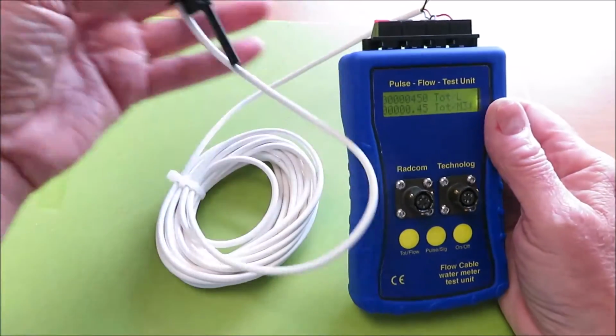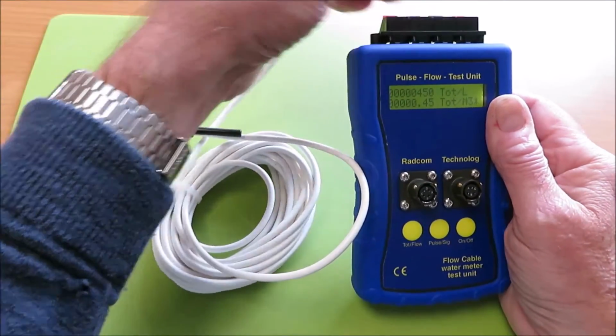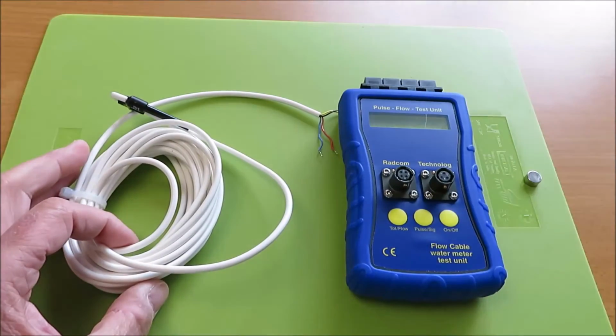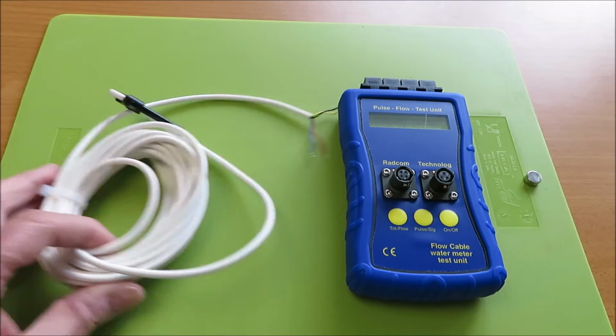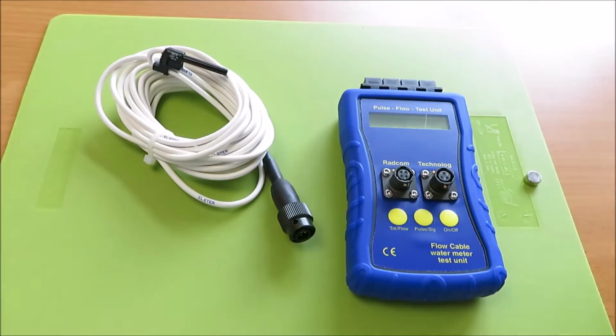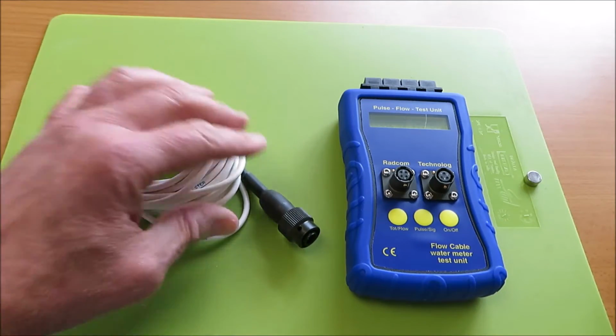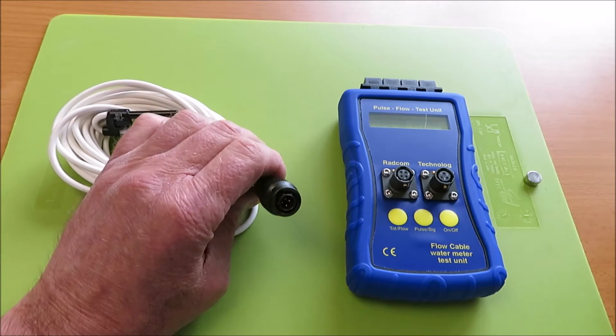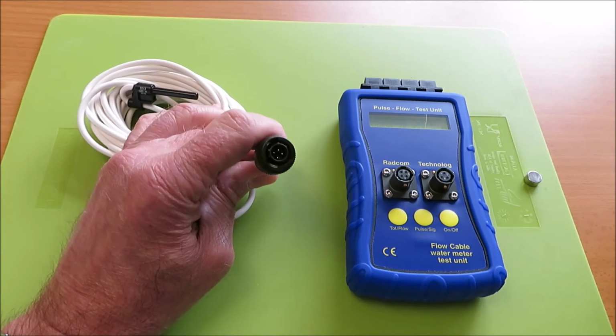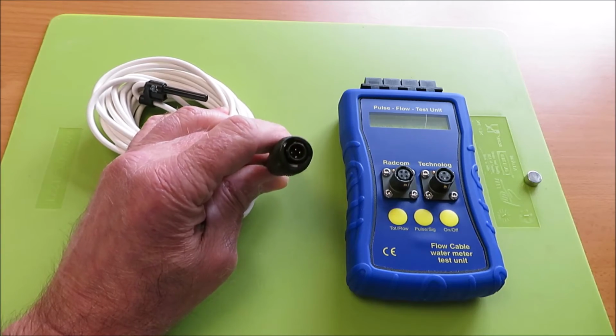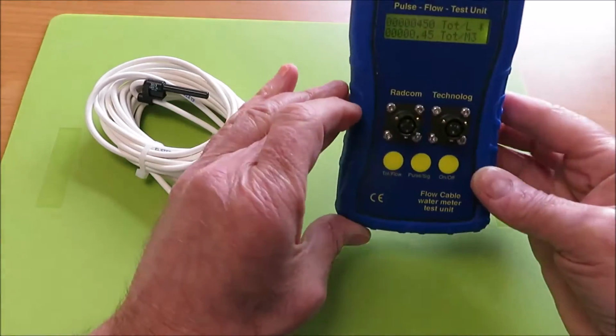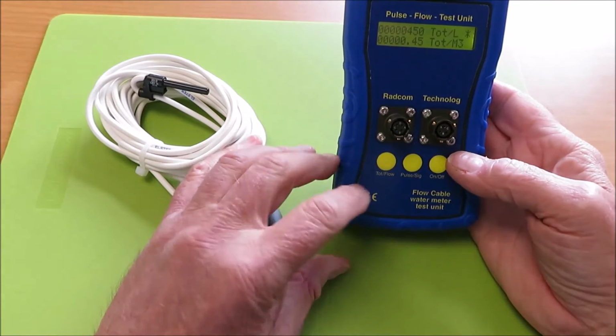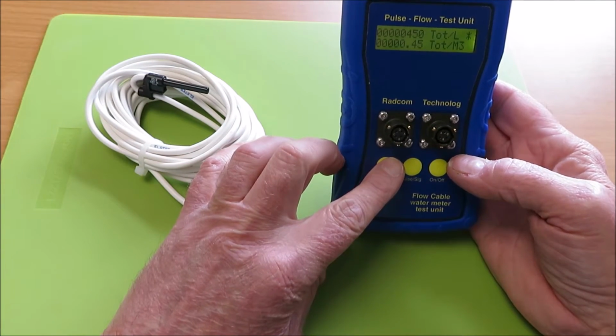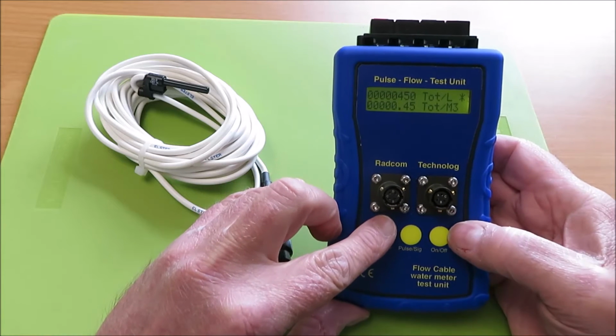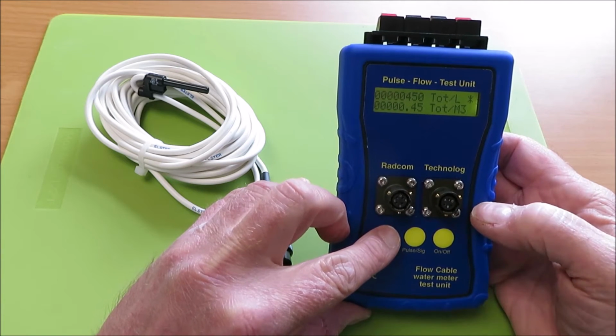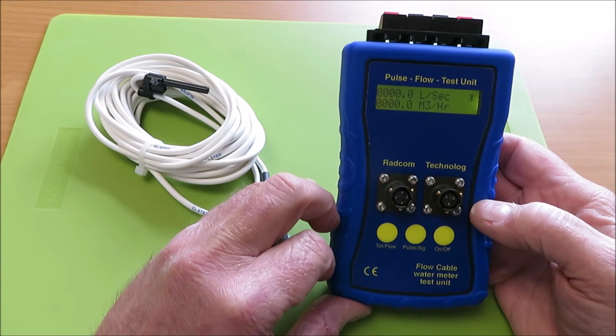Now equally, what you could do is remove those connectors, and as they say on Blue Peter, here's one I made earlier, and this particular flow sensor, they're exactly the same type. this probe has the Radcom 4-pin connector, and all I would do to test this, as we're in total there, you can see that it's recorded the pulses that I put through the meter. If I go back to the flow rate, you'll see that it's zeroed itself.